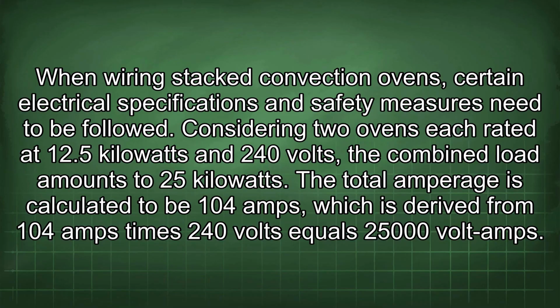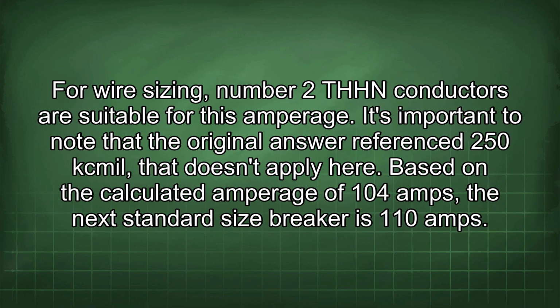When wiring stacked convection ovens, certain electrical specifications and safety measures need to be followed. Considering two ovens each rated at 12.5 kilowatts and 240 volts, the combined load amounts to 25 kilowatts. The total amperage is calculated to be 104 amps, which is derived from 104 amps times 240 volts equals 25,000 volt amps. For wire sizing, number 2 THHN conductors are suitable for this amperage.